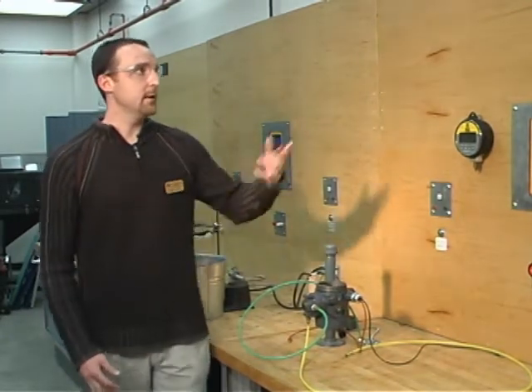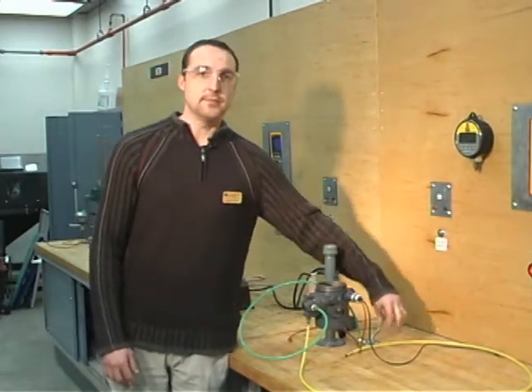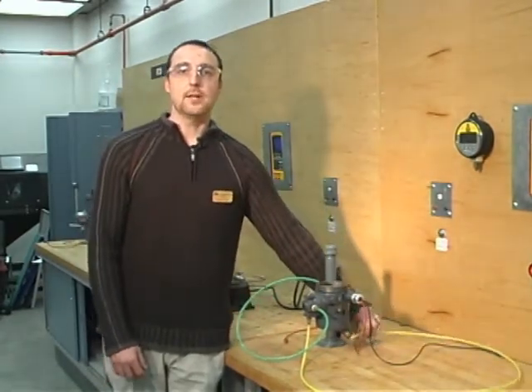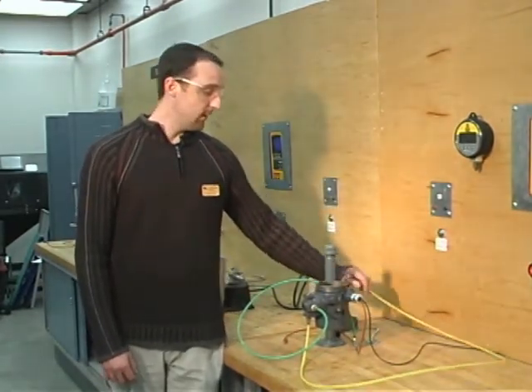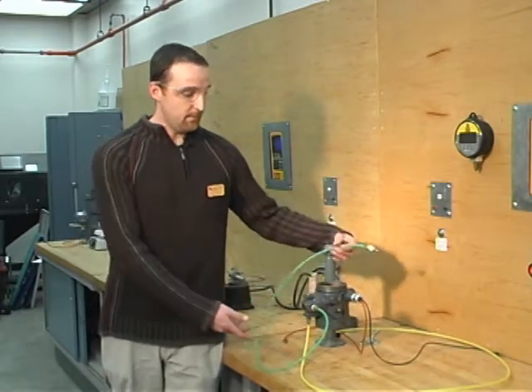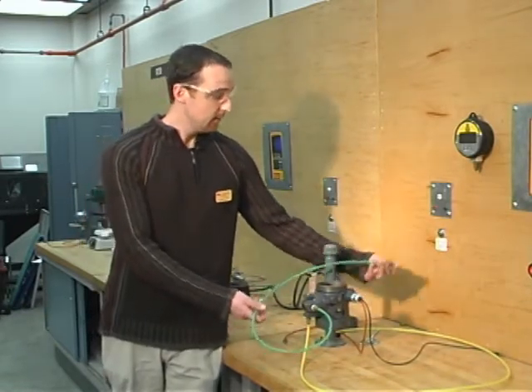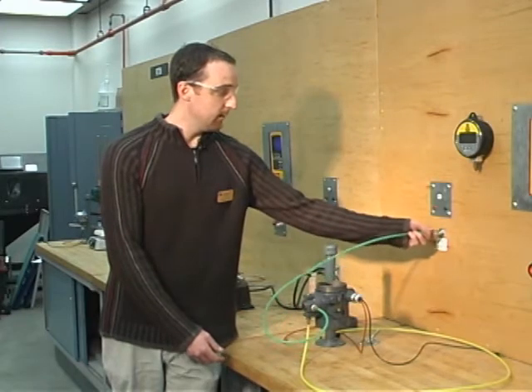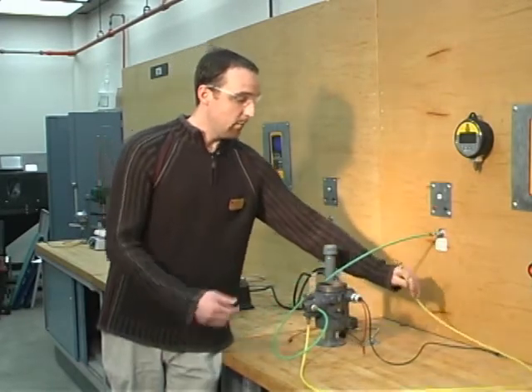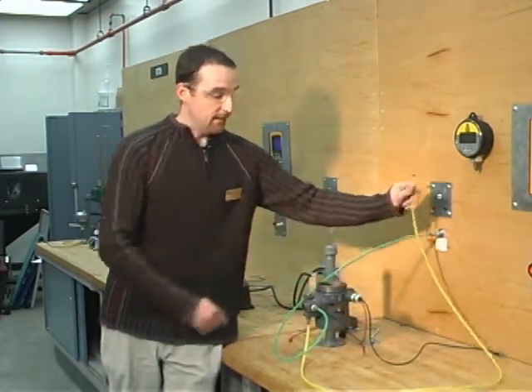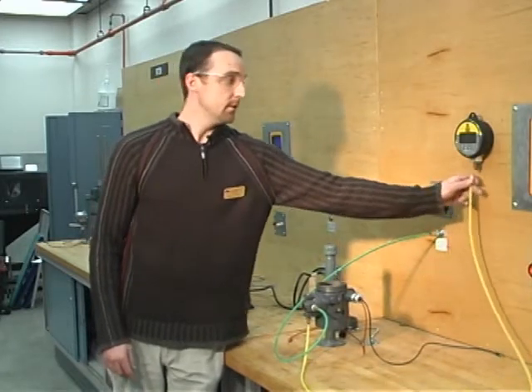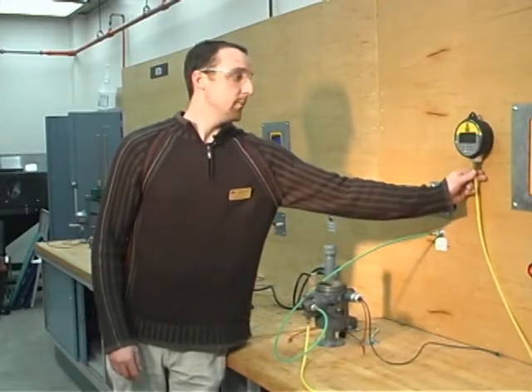Today we're going to be working on the I to P, which is also known as a transducer. We're going to have to plumb up our transducer. First, we're going to plumb up our supply air to the 20 psi port, and we're going to hook up the output from our transducer to a pressure indicator.